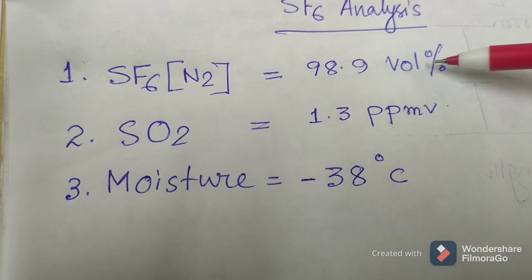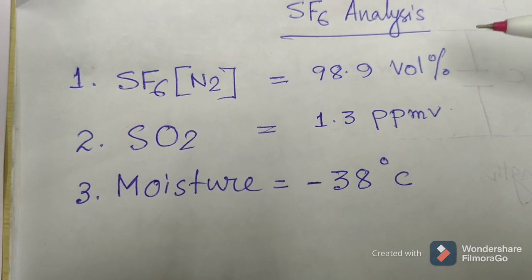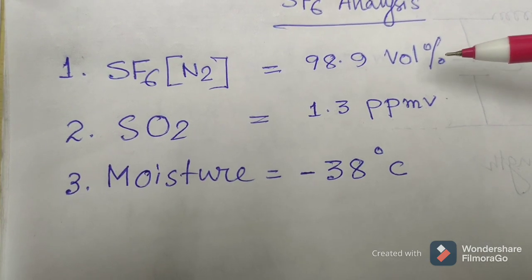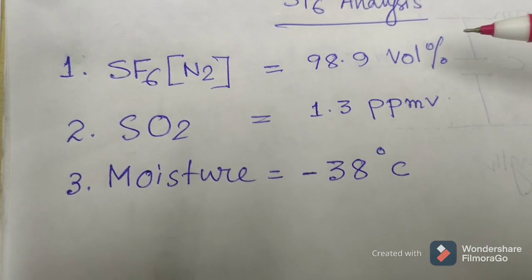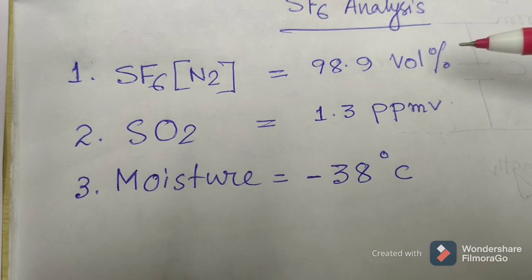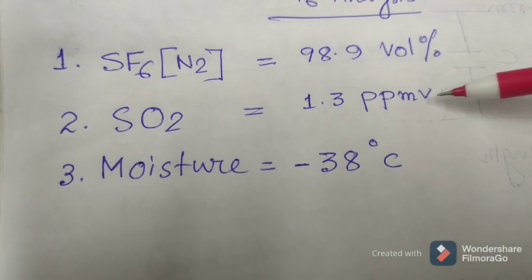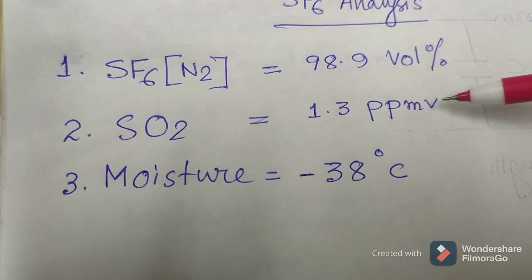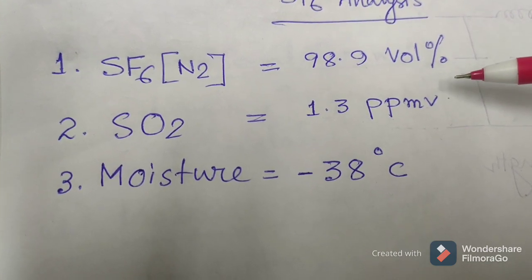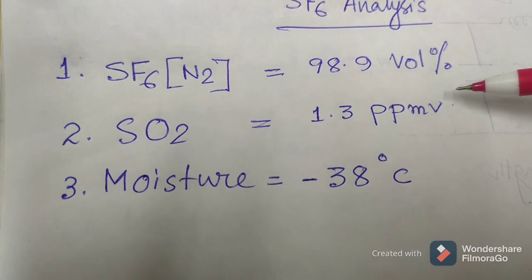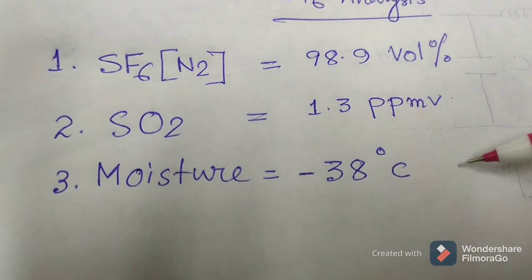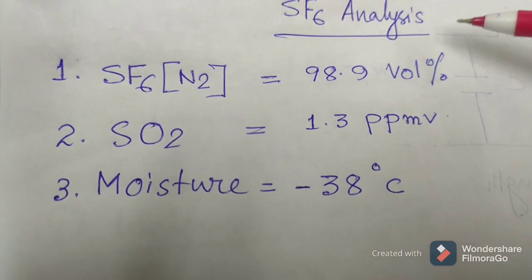We have to analyze the SF6 quantity present after lots of arc quenching or arcing inside the interrupters, how much SO2 sulfur dioxide gas has been generated inside the interrupter cases, and also the moisture inside the interrupter.